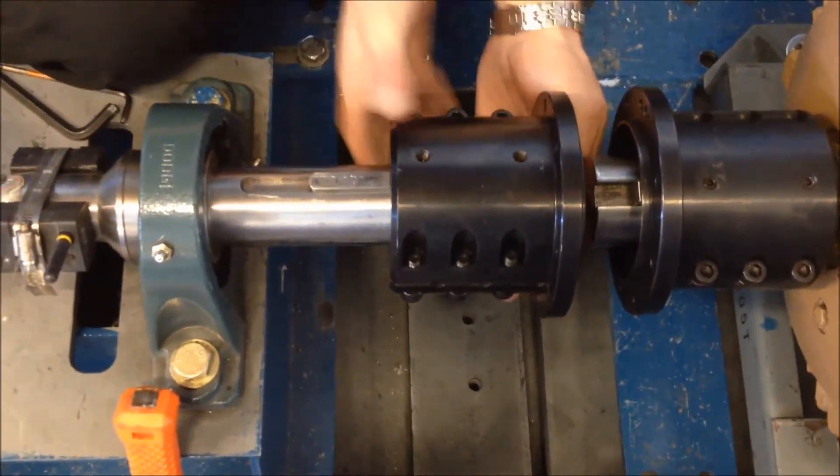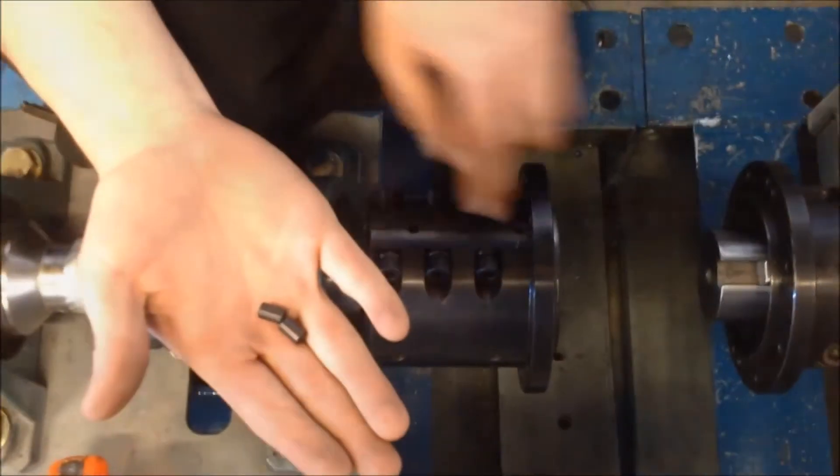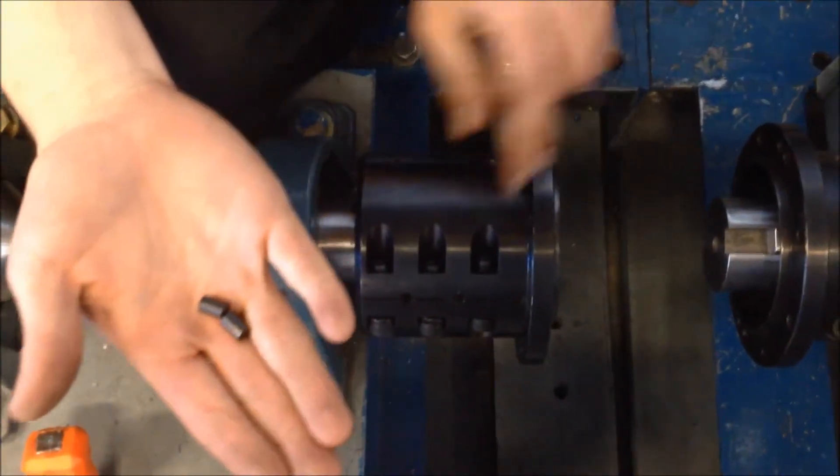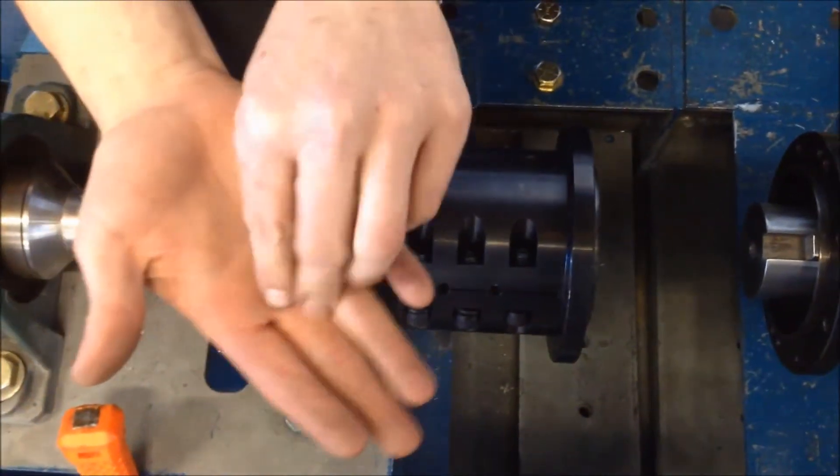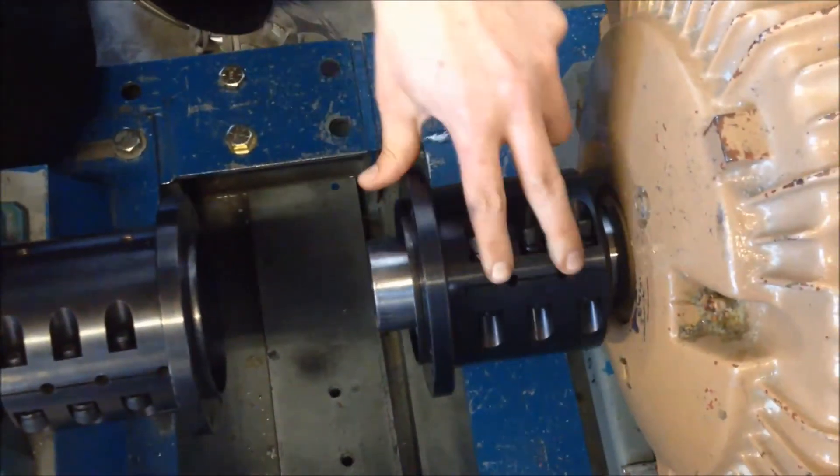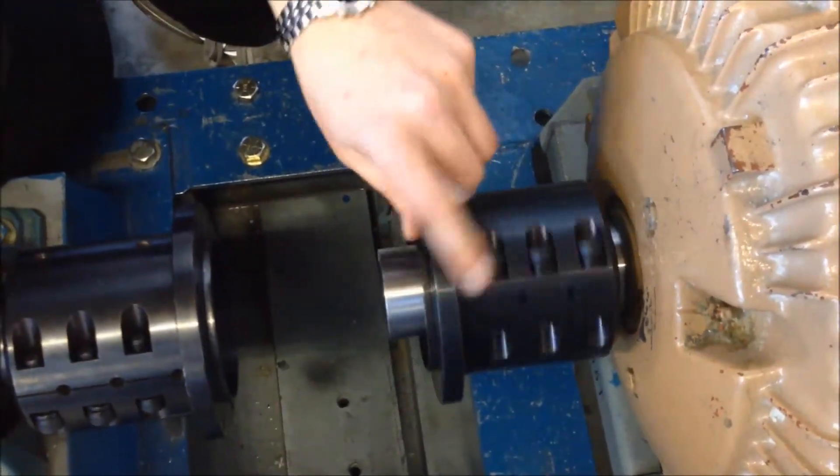Inspect both hubs for machining dowel pins. These pins may have inadvertently been left in after the boring process. The pins have to be removed in order to allow the hub to clamp onto the shafts properly.